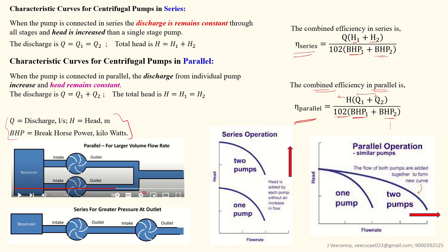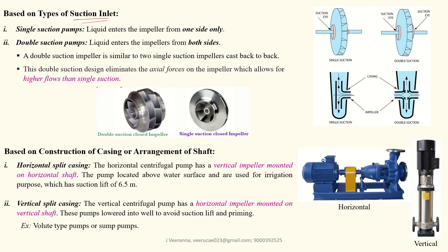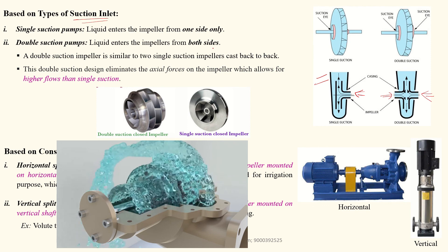The next classification is based on suction type. In a single suction pump, liquid enters from only one side. In a double suction pump, water enters from both sides. The double suction impeller is equivalent to two single suction impellers placed back to back on a common shaft. This double suction design eliminates the axial force on the impeller, which allows for higher flow rates than a single suction design.